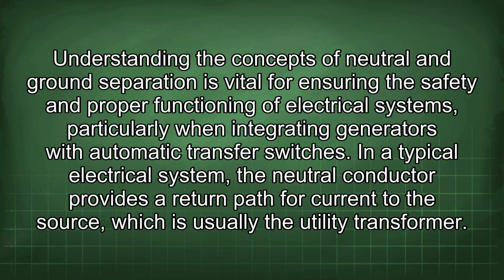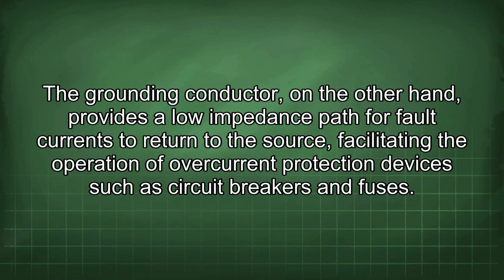Understanding the concepts of neutral and ground separation is vital for ensuring the safety and proper functioning of electrical systems, particularly when integrating generators with automatic transfer switches. In a typical electrical system, the neutral conductor provides a return path for current to the source, which is usually the utility transformer. The grounding conductor, on the other hand, provides a low impedance path for fault currents to return to the source, facilitating the operation of overcurrent protection devices such as circuit breakers and fuses.